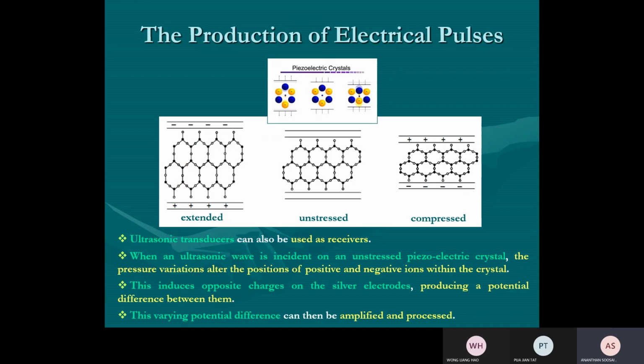The ultrasonic transducer can be used as a receiver. First we talked about producing ultrasound, which is transmitted to the body. Now the echo will be received back by the transducer, so the transducer acts as a receiver, detecting the ultrasound. Once they send the pulse by electric field, they shut down the electric field and wait for the echo to come back. When the echo is received, no voltage is applied to the crystal, no external voltage is applied. And the echo is received, what happens?